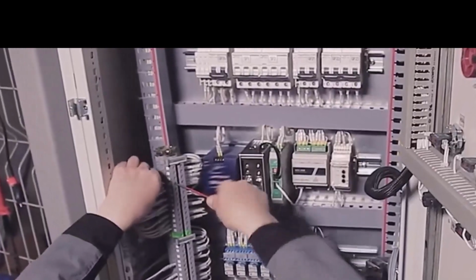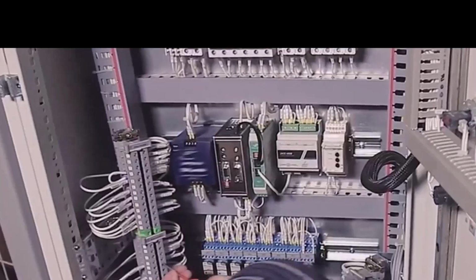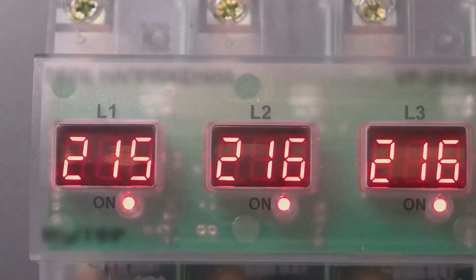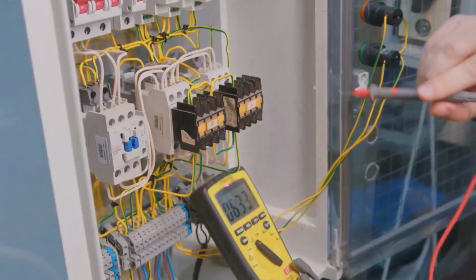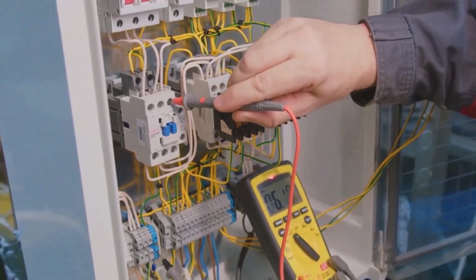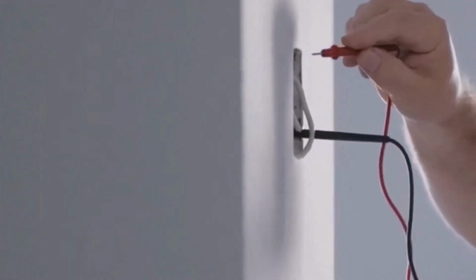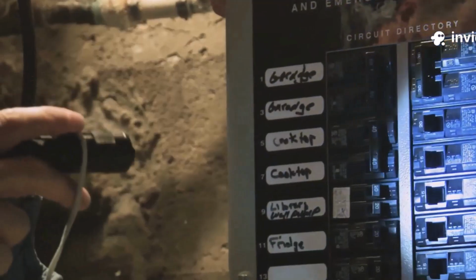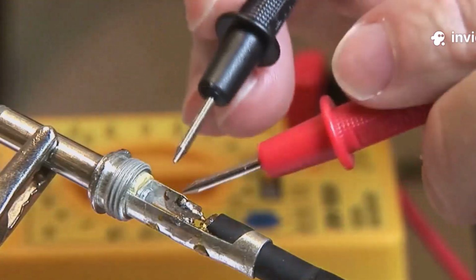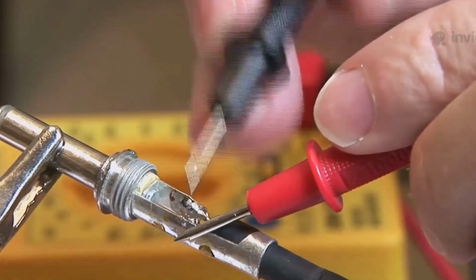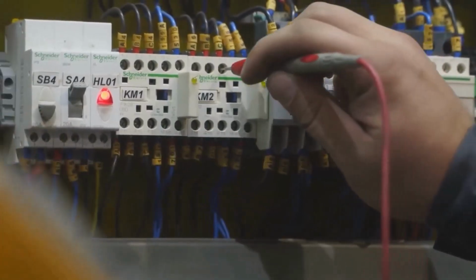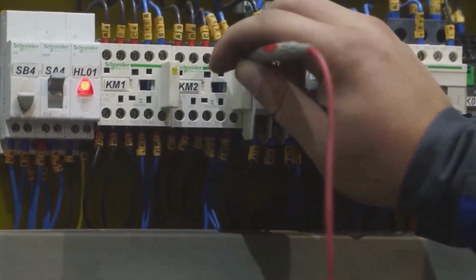The neutral point is the secret ingredient that makes the Y connection so versatile. Because it's connected to all three phases, it acts as a stable reference. In a perfectly balanced system, where each phase is doing the exact same amount of work, very little current actually flows through this neutral wire. However, the real world is rarely perfect. If the loads on the different phases are unequal, the neutral wire provides a safe path for the unbalanced current to return to the source. This helps keep the voltages across each phase stable and prevents potential damage to connected equipment, making the whole system more reliable and safe for everyday use.